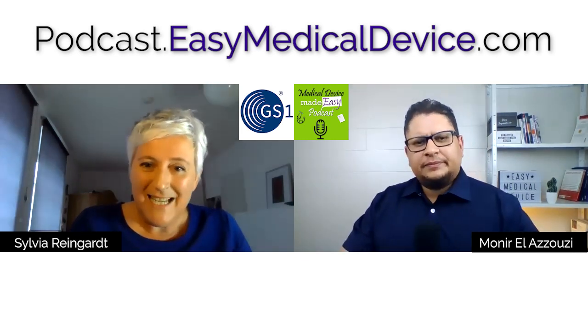The basic UDI-DI connects to the UDI database, but also to the registration of devices, the summary of safety and clinical performance, the certificate of free sale, the technical documentation, the EU declaration of conformity, and the certificate issued by a notified body. So it's a really new concept. Every supplier has to be aware of that, and it will have immense impact on any UDI implementation project. That's what we are thinking.